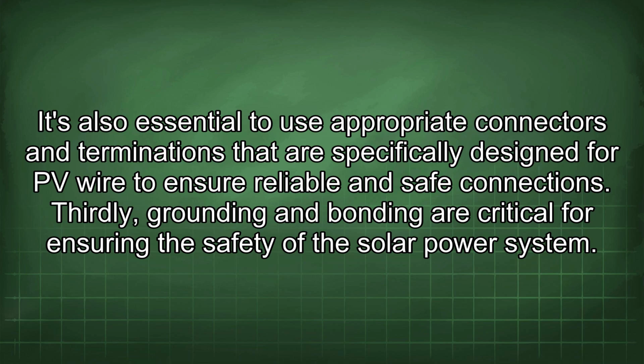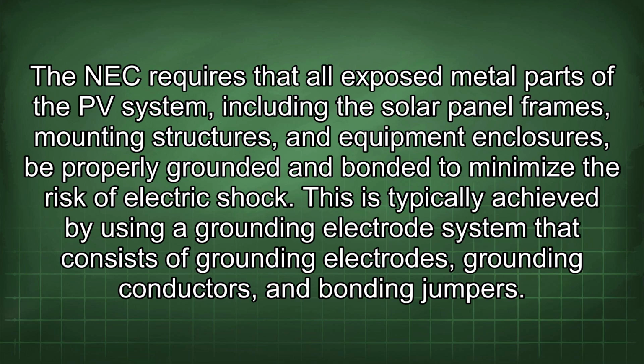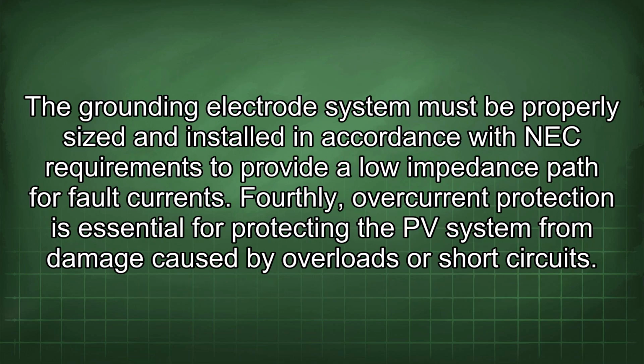Thirdly, grounding and bonding are critical for ensuring the safety of the solar power system. The NEC requires that all exposed metal parts of the PV system, including the solar panel frames, mounting structures, and equipment enclosures, be properly grounded and bonded to minimize the risk of electric shock. This is typically achieved by using a grounding electrode system that consists of grounding electrodes, grounding conductors, and bonding jumpers.